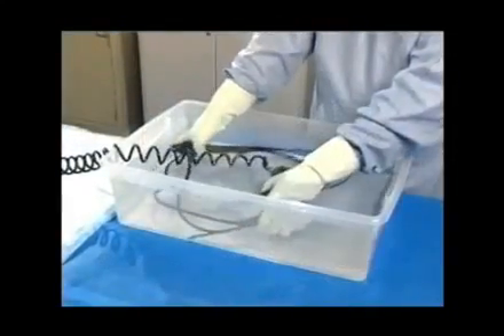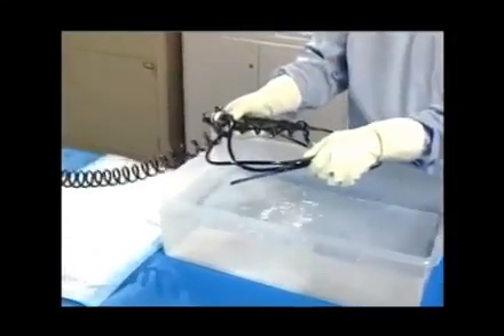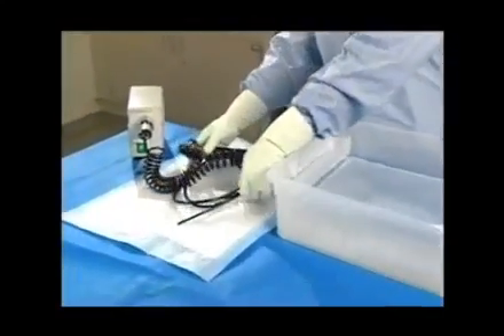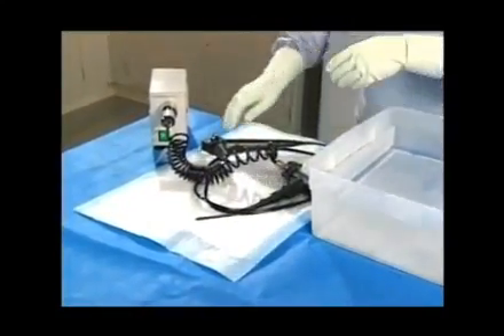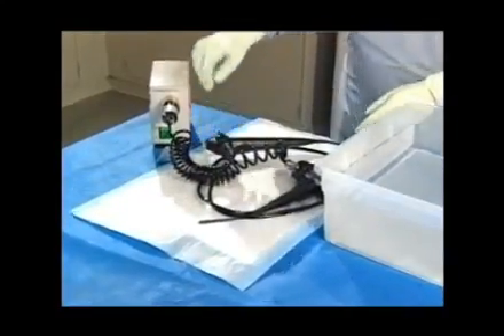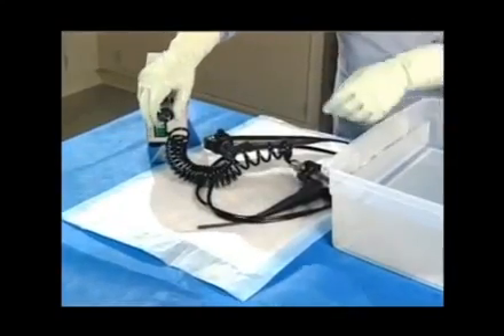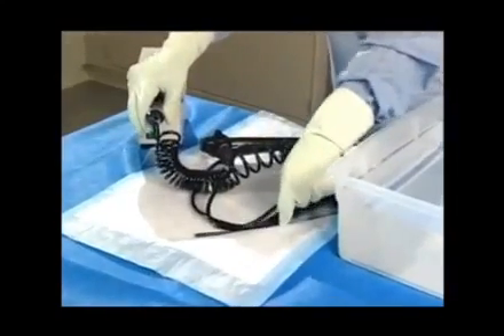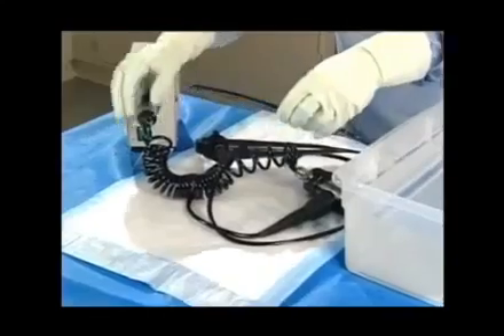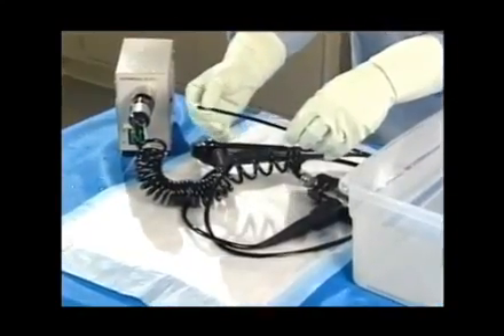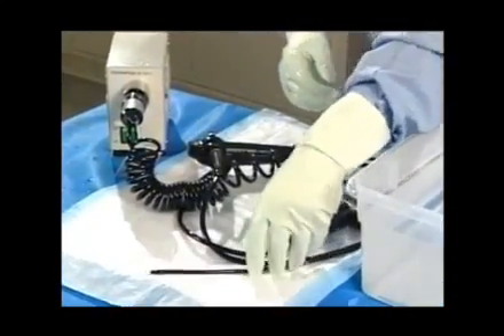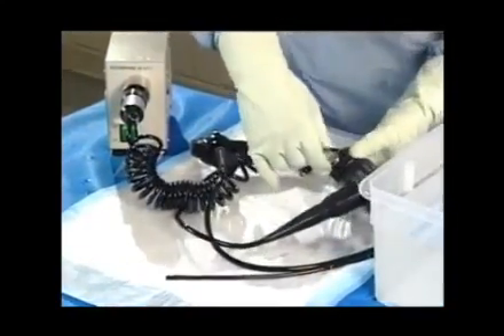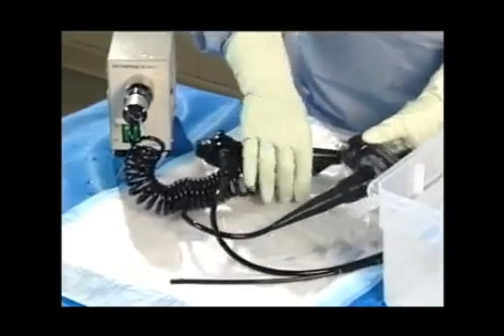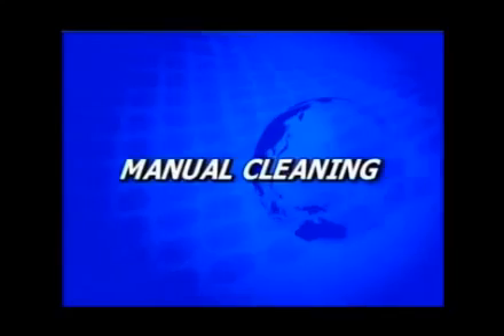If no leaks are observed, remove the bronchoscope from the water. Turn off the pump, disconnect the leakage tester from the air supply, and wait for the bending section rubber to return to its normal size. Detach the leakage tester from the water-resistant cap. Leakage testing is now complete.